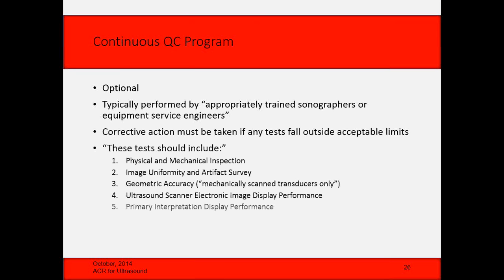So the ACR may ask you to see those records at some point as part of their auditing. And my suggestion is this could be part of the annual survey. The annual survey and the PM should overlap, right? You should be doing basically some of the same tests or these same tests. So the schedule and activities or the proof of PM performance don't need to be submitted, but as I said, they may ask you for them. The OEM documentation may have a schedule and activities performed, but usually not, unfortunately. And actually the GE user and service manuals contradict each other on what the schedule should be. One says you don't need any, the other one says one per year.